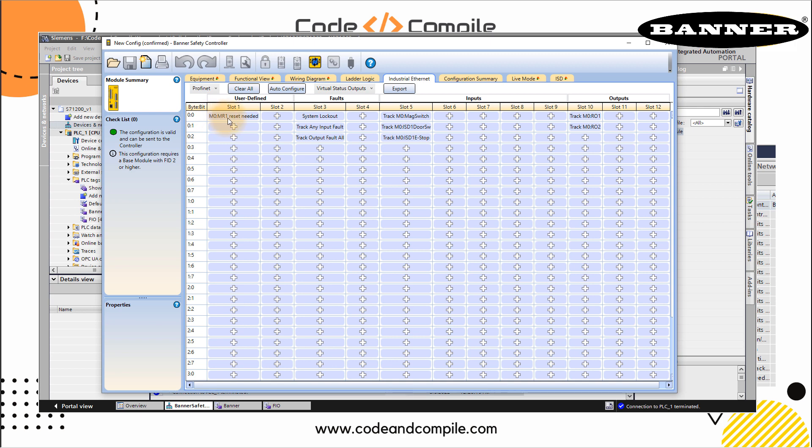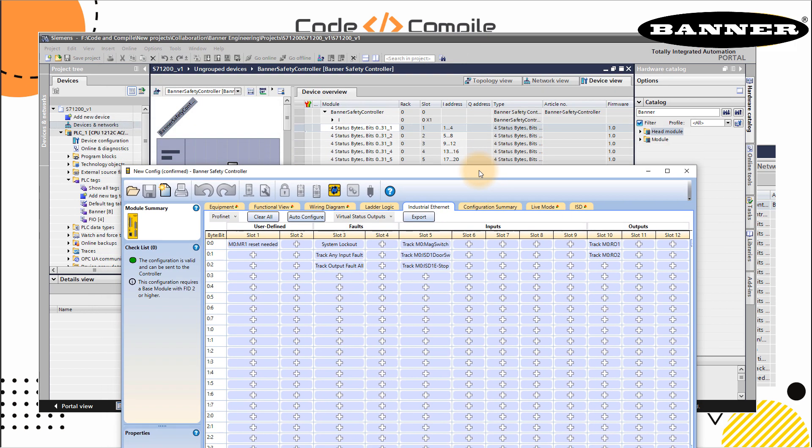Slot one, you can connect or relate that with the slot one which is here. Slot one says it's M0, column MR1 reset needed. And that's my first bit. If you see this one here, slot one is input address I1 to I4. So the address of this function is I1.0. So this is I1.0. And rest we don't need to read because this is not defined here.